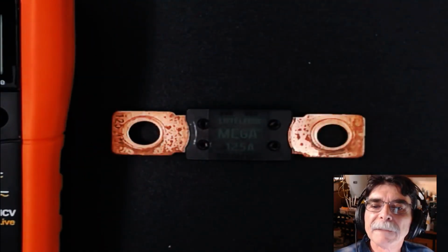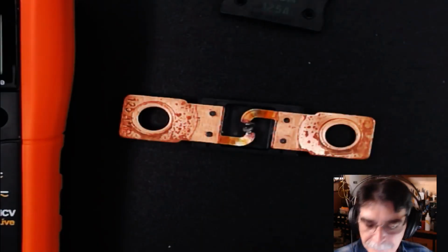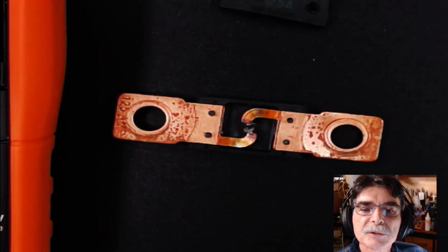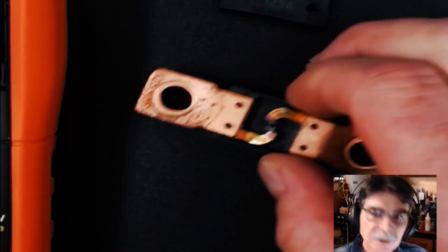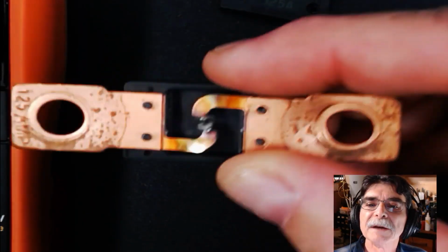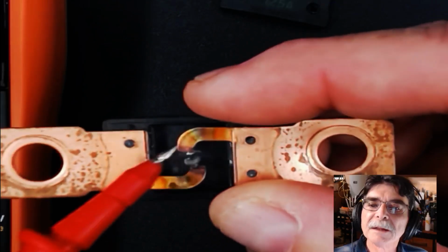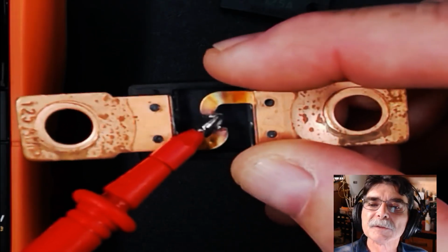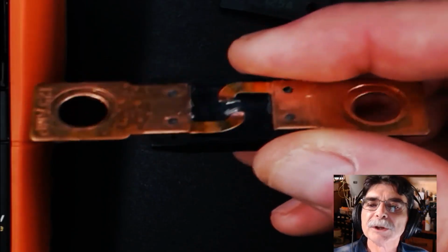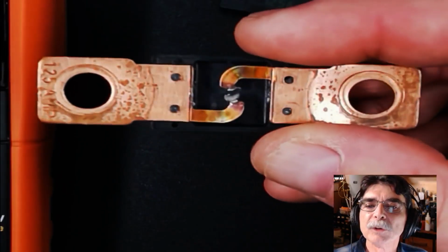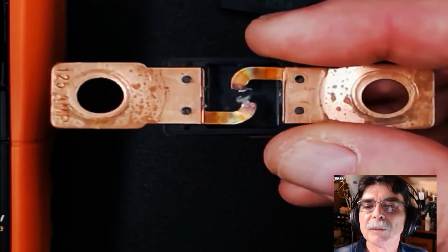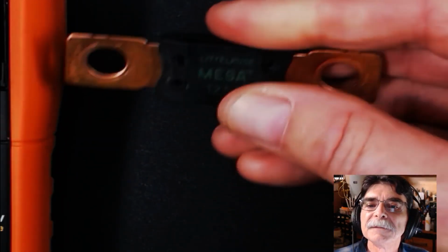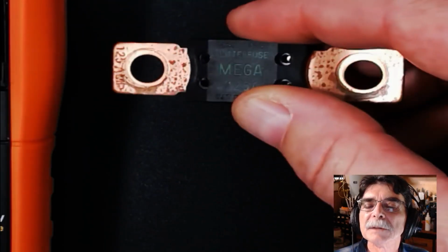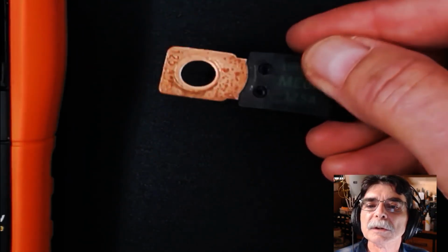Here's something cool. Here's what it looks like inside. A mega fuse is really just a large fuse. You can see that the fusible element in the center here is burnt. So this fuse is open. And the only way you would have known that is to either A, check it via voltage, or B, remove the fuse or power and check it for continuity. So mega fuses have no visual way of asserting whether they're open or shorted.